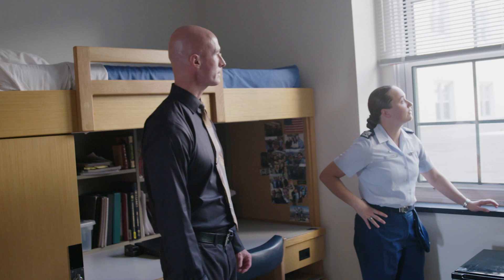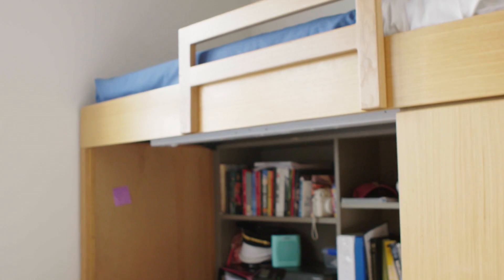The temperature variation might be because one part of the dorm is really hot right now even though it's at the same set point, while another feels cool because it's lower and has no sun on it right now. That could get back to the idea of individual controls, having a little control over the room. Some of the findings they had did represent some worthwhile follow-up work on our part, but it also demonstrated the challenge we have dealing with historical buildings and monumental structures.